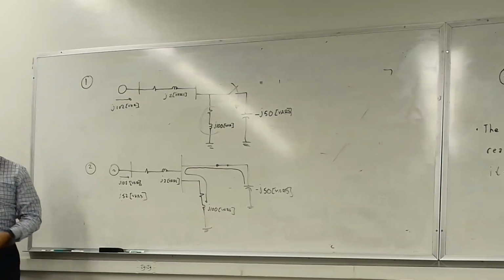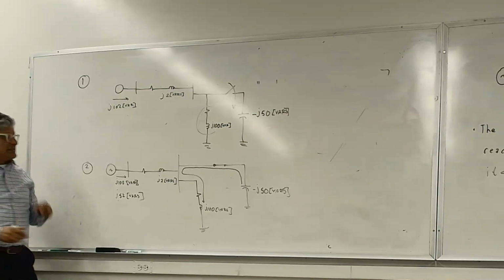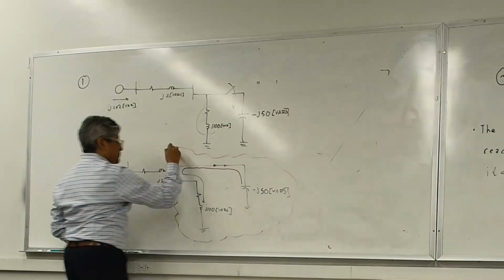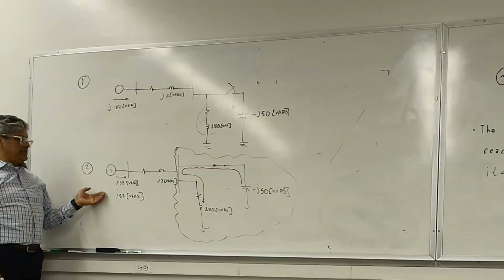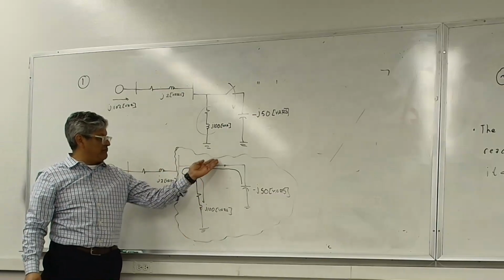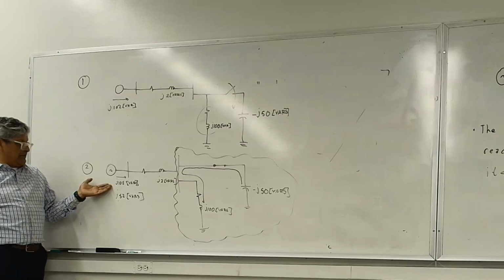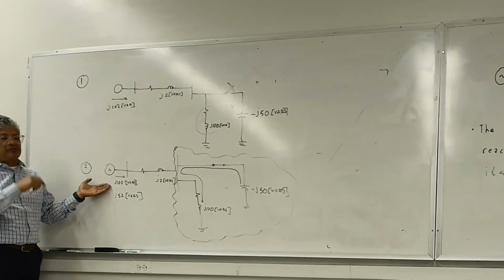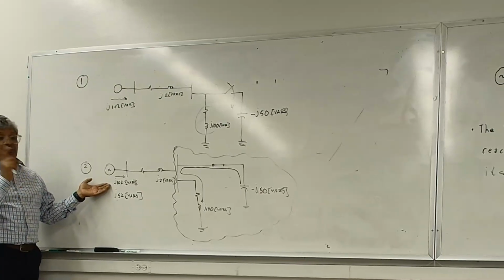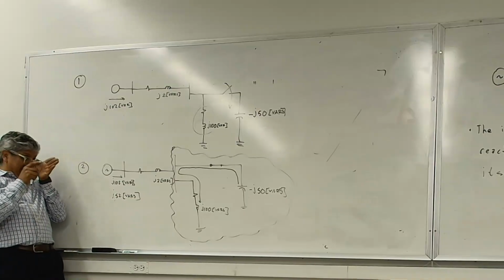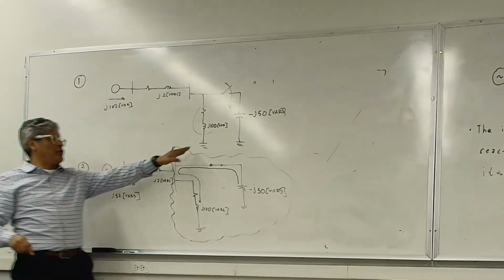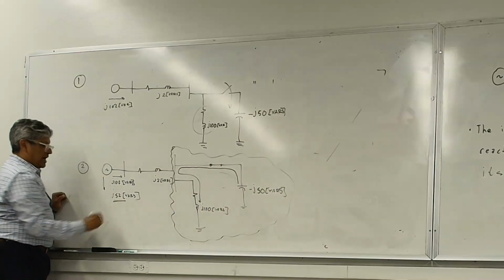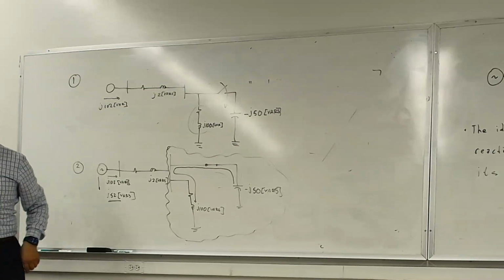Everybody okay with that? So basically, if you look at this as a black box, a factory, before you close that switch, the utility was telling you, I'm giving you 102 VARs. I don't know what the real power is, but assume that the power factor was really bad, like 0.3. That's what the utility sees. When I close this, the utility says, ooh, my vars are gonna go down. Now you're asking me only for 52 instead of 102.